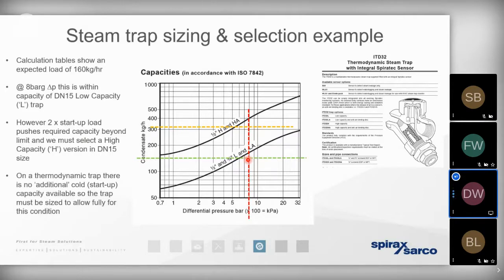In other words, if we have got that secondary auto drain in situ. If we haven't, and if we need the trap to accommodate both the running load and the warming up load, we need to double that 160 kilograms per hour to 320, and that then tells us how we've sized the appropriate trap. So if we'd used the first of the two trap types to move both the running load and the warming up load, you can appreciate it would be hugely undersized.